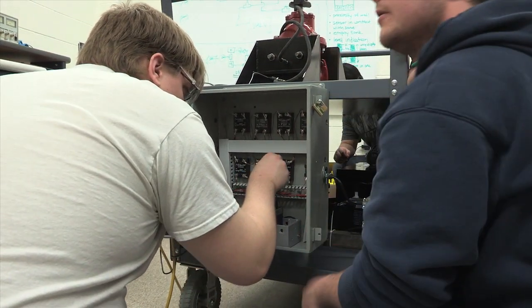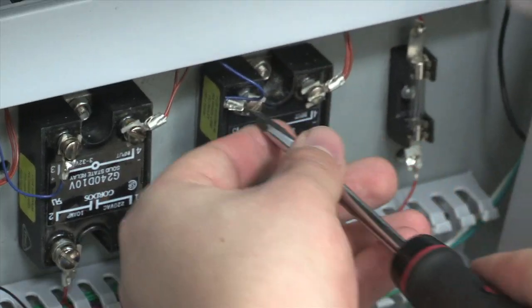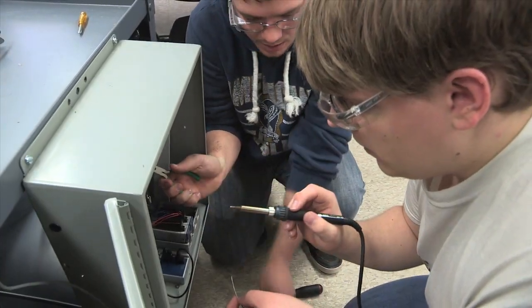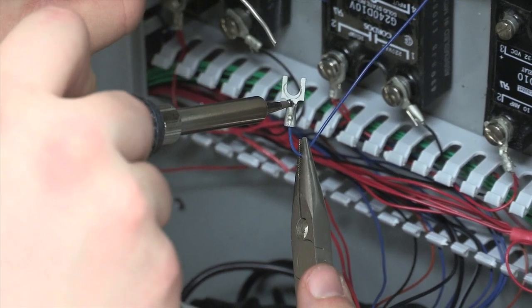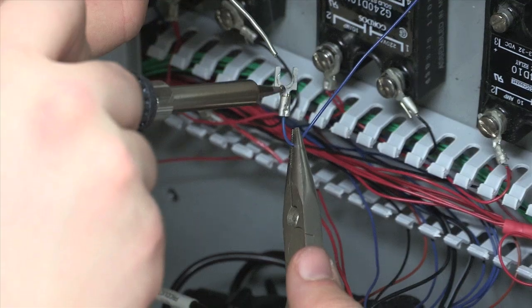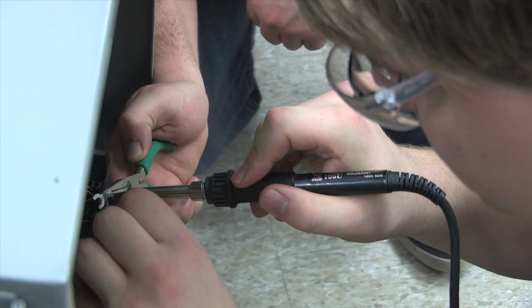What we're working on is primarily the instrumentation for automating this process, and also being able to test both sides of the valve in one fixture rather than disassembling it and turning it around. These valves are heavy — between 75 and 150 pounds for the sizes we're talking about. There's a lot of manual labor, and you get into ergonomics of repeated tasks as well. So if we can cut those movements down by half, that should also cut down the time.